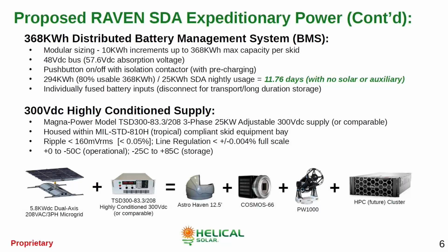So with adding up to 368 kilowatt hours of distributed BMS to that, it will be push button start and shut down and enable safe to touch and maintain 48 volts DC system components. And 80% of that usable capacity, which is around 294 kilowatt hours, would result in about 11 3/4 days of reserve at 25 kilowatt hours per day for the SDA platform nightly usage. We would pair that with a 300 volt DC highly conditioned supply from Magna Power, the TSD300, and run that off of the 208 volt 3-phase, and that would provide low ripple and superior line regulation.